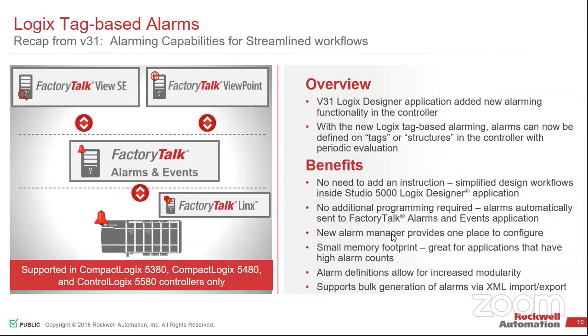We're probably closer to the 1,000 to 2,000 range of how many alarms we would want in a controller. And for everything else, where we can go to the 10,000 level, that would still be on the HMI side, because those are your non-critical, process-based alarms, like a lot of the high temperature ranges where you just want that as informational. We can mix and match all day long. So now we have that built into the controller. I'm taking a little bit more memory, and it only exists in version 31 and above. Again, it's a 500 millisecond scan rate on anything inside of it.